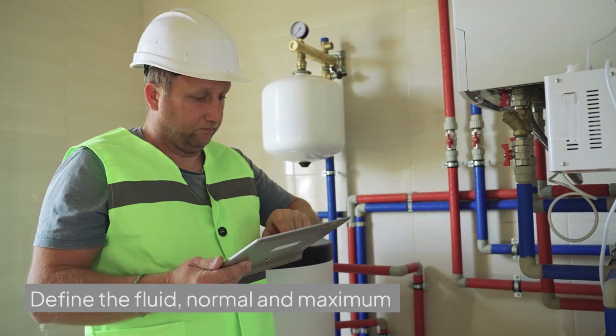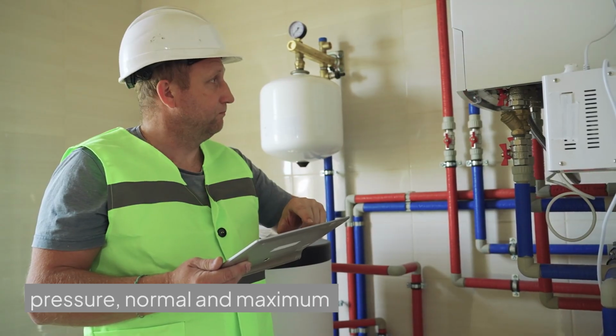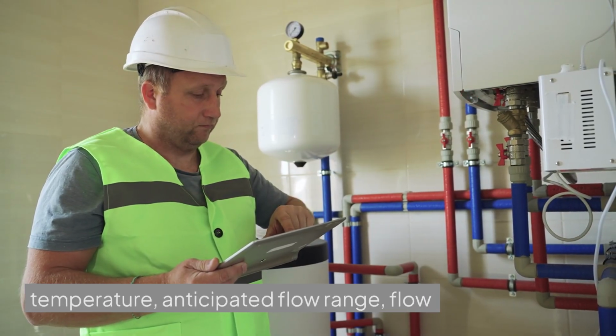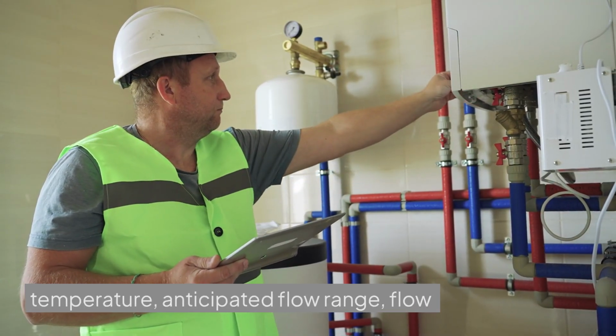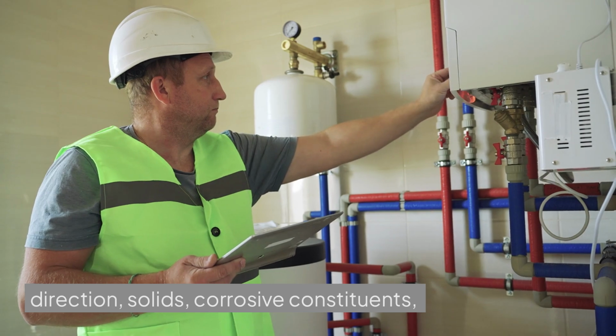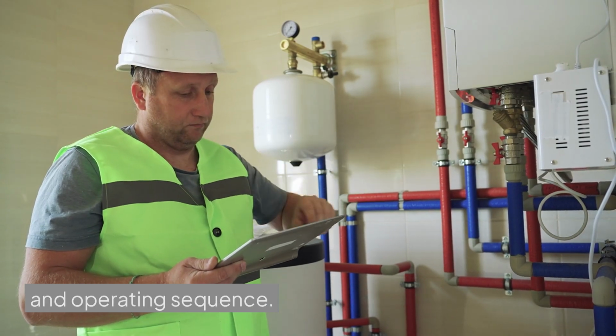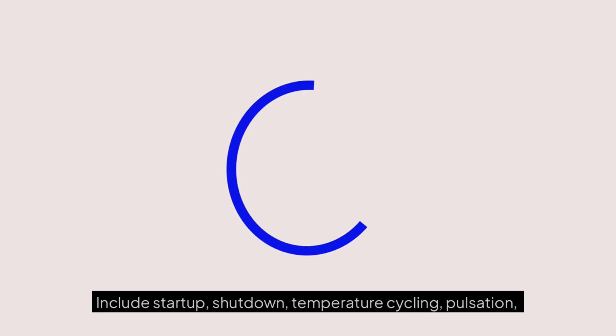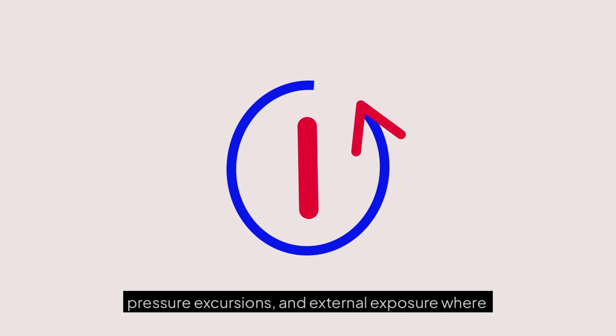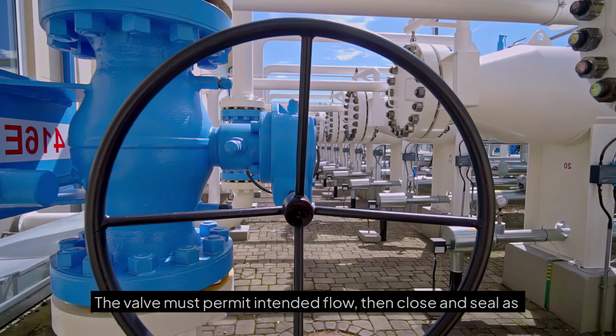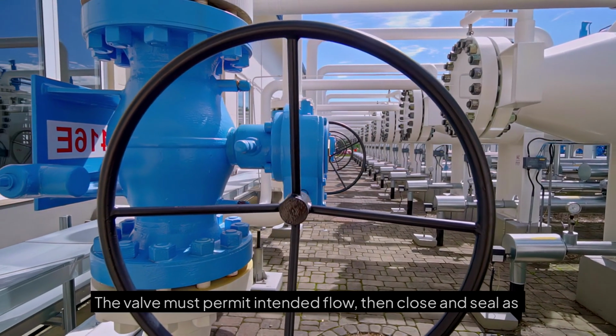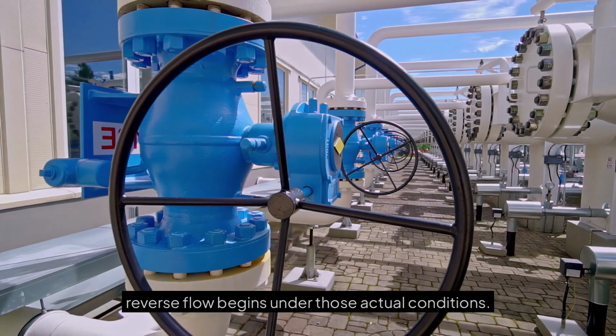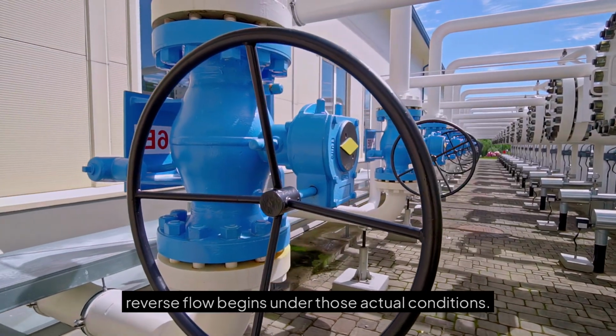Define the fluid, normal and maximum pressure, normal and maximum temperature, anticipated flow range, flow direction, solids, corrosive constituents, and operating sequence. Include startup, shutdown, temperature cycling, pulsation, pressure excursions, and external exposure where relevant. The valve must permit intended flow, then close and seal as reverse flow begins under those actual conditions.